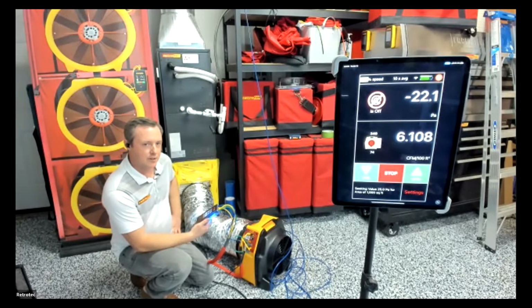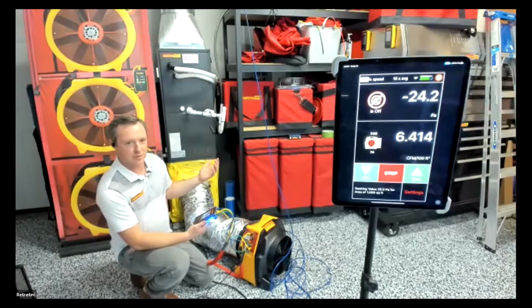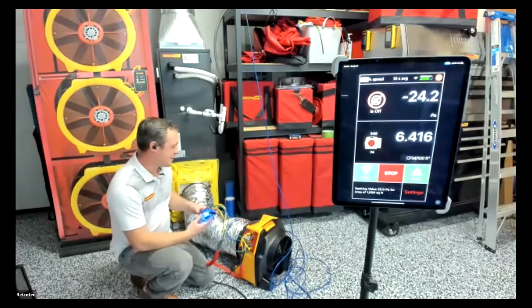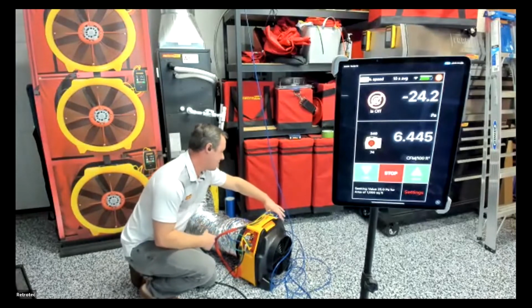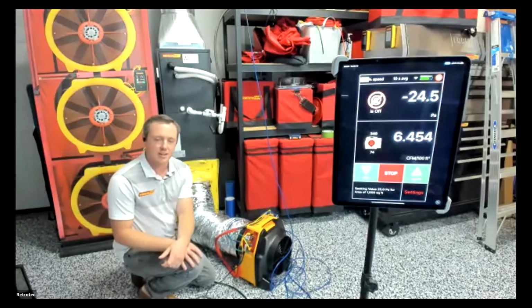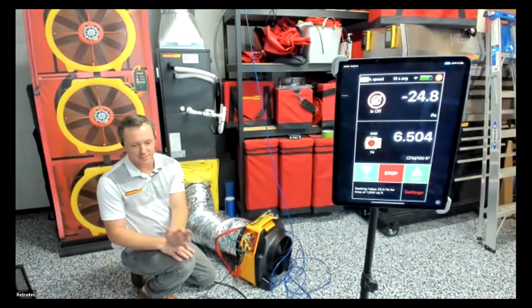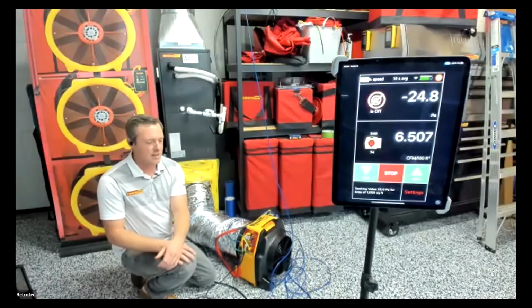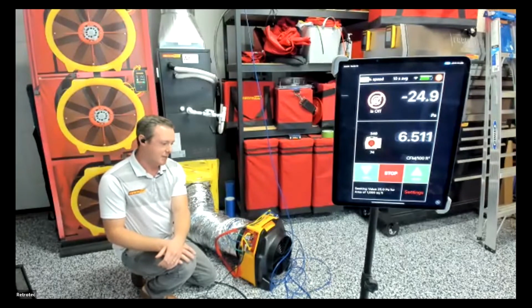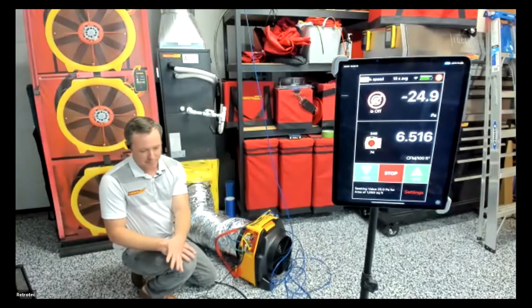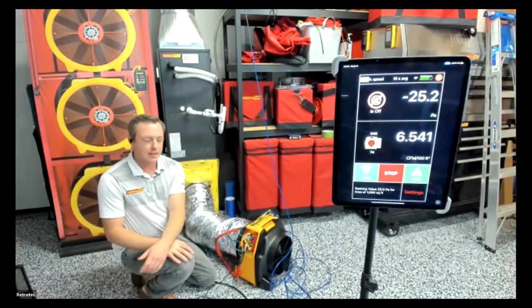And notice on the bottom, we have that CFM per 100 square feet selected. So that's going to give us that percentage that we're looking for. So we're already past our target, if 6% duct leakage was what we wanted. And I say 6% because if you're looking at a lot of different state codes or regional codes, 6% is a pretty common number. Some would go down as low as 4. I think Virginia just adopted 4% total leakage this year. Some more rigorous building performance standards go down to 3.